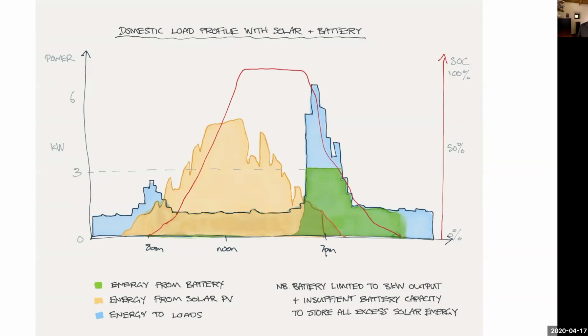You might have the reverse problem, where your PV is way too big and your battery is fully charged by 1 o'clock in the afternoon. Now, that's actually not a problem - you could say it's a good problem to have, because oversizing a PV system gives you a lot of flexibility for change in demand as the customer starts to use more energy over time, and on less than ideal days you're still getting a large amount of renewable energy input. So oversizing is not a design problem, maybe just a cost consideration, but undersizing your solar compared to your storage is a performance issue. Unless you're prepared to use a generating set to finish that charging process, you may damage particularly some chemistries like lead acid.